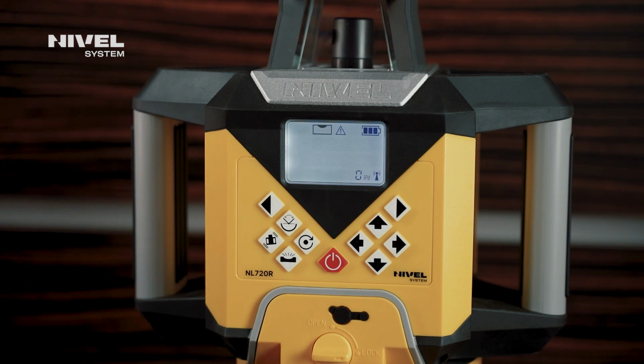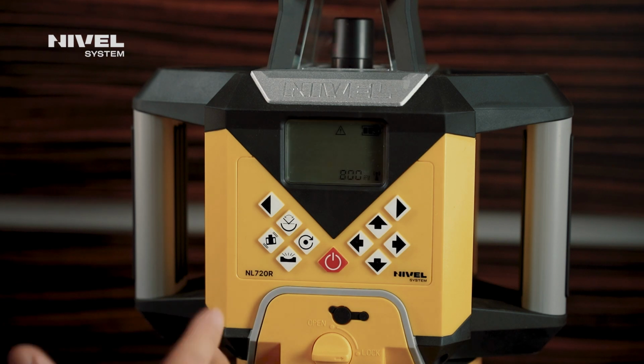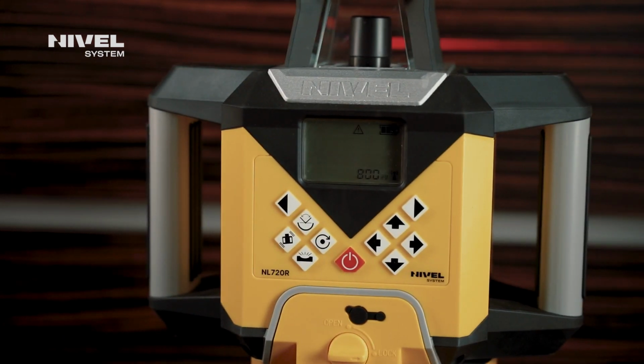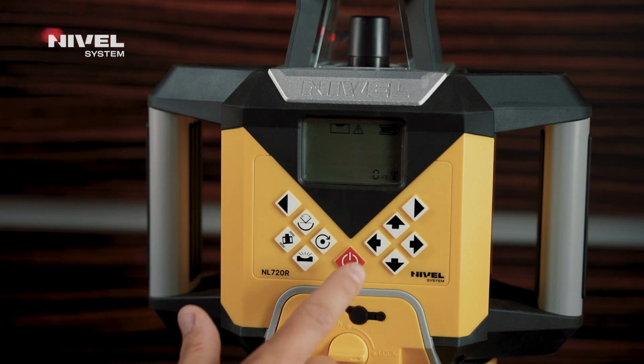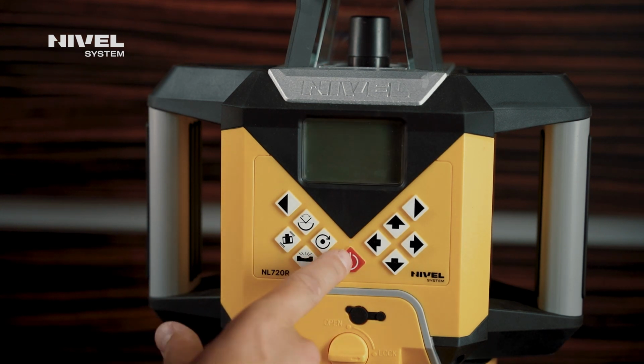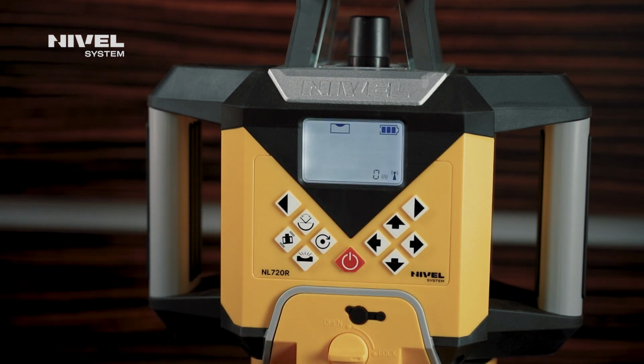The tilt sensor protects against considerable vibrations or sinking lower into the ground. In such a case, when the laser changes its position, it may mean that its measurements are incorrect. Therefore, when the tilt sensor is used and larger vibrations occur, the equipment stops working and does not restart. It is necessary to turn off and turn on the equipment, which then performs auto-leveling.